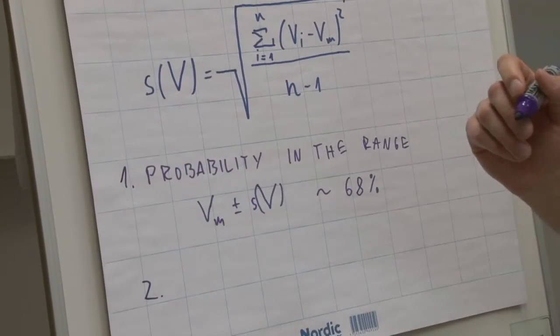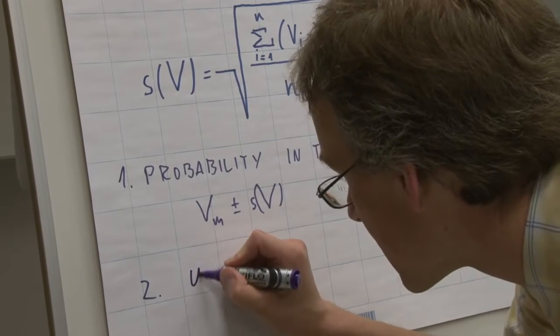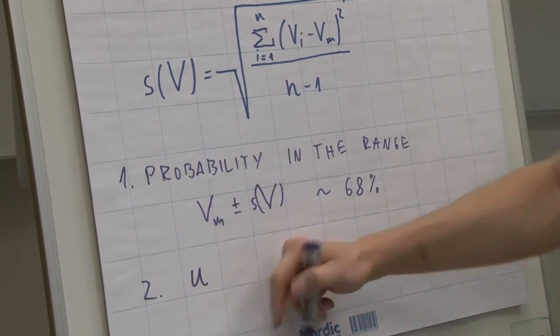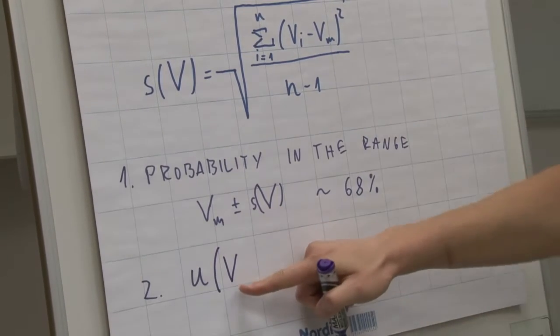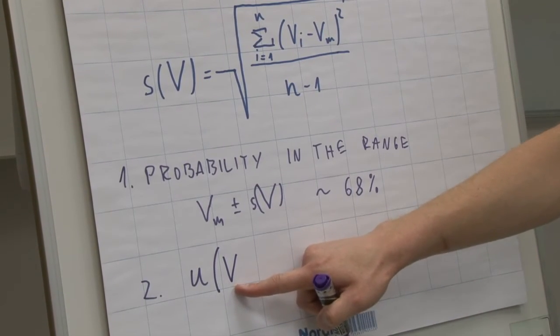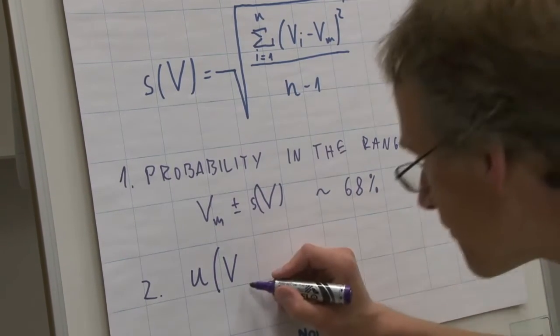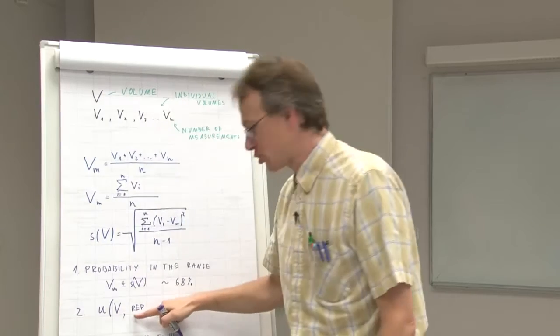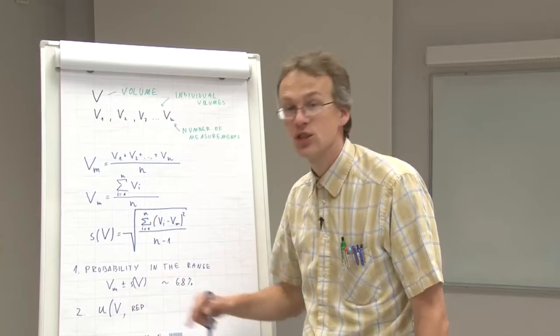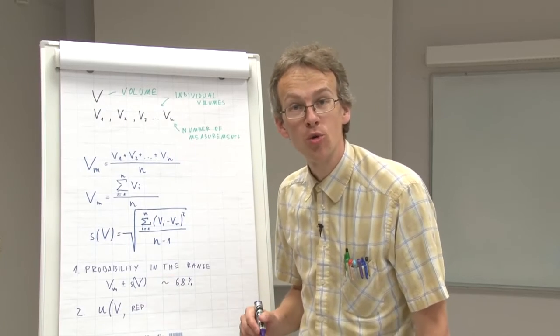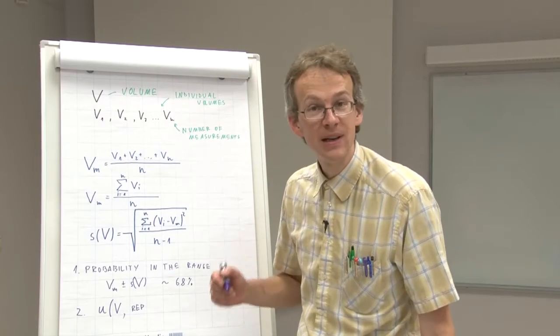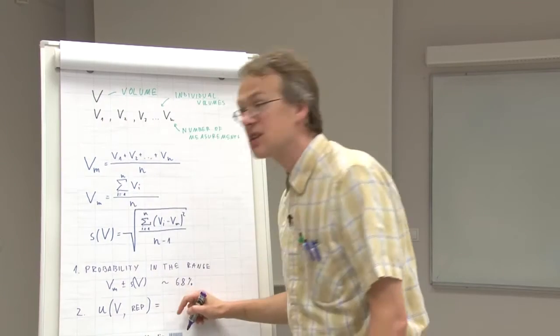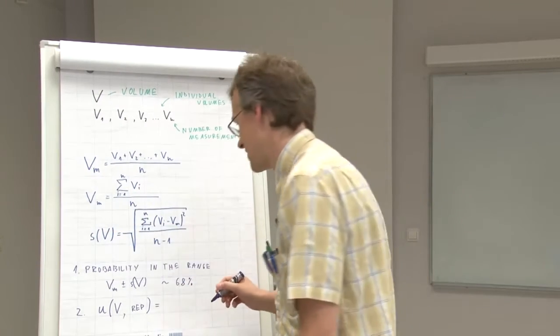We can speak about the standard uncertainty denoted by small u of this volume, which we measure by pipetting due to repeatability. This is one of the uncertainty components, the repeatability uncertainty component, and this is equal to this same standard deviation.